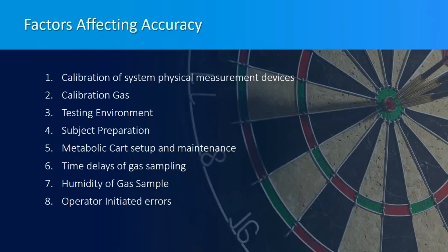Metabolic carts also have many other factors that affect accuracy, including calibration of the system physical measurement devices, the calibration gas, the testing environment, subject preparation, metabolic cart setup and maintenance, time delays of gas sampling, operator-initiated errors, and humidity of the gas sample.